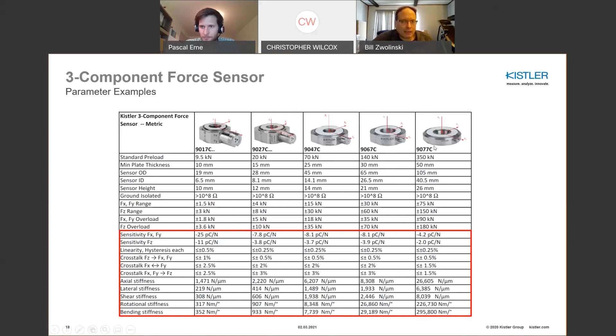So all these sensors here you see are going to need a preload, and that's why you see a center hole here. They accept a preload bolt, and I'll get into a little bit more of how that's done. If that's not your cup of tea and you don't want to do preloads, and you can live with the added height of a force link sensor, these are actually preloaded at the factory. They have a top and bottom flange, and they come with a calibration certificate, of course. And these can be easily integrated as well within, say, two parallel plates. I mean, the parameters are similar. Sensitivities, linearities, crosstalks, and stiffnesses are all provided for force links as well.